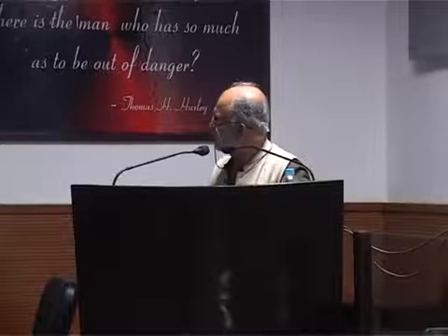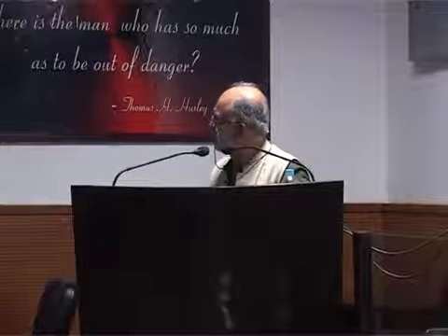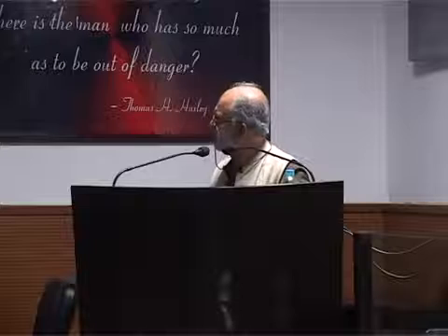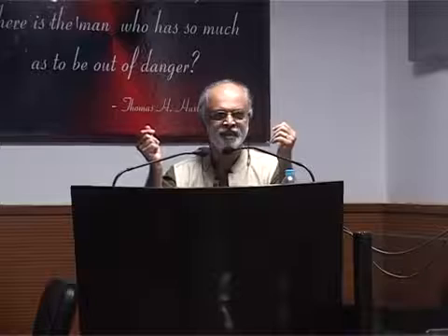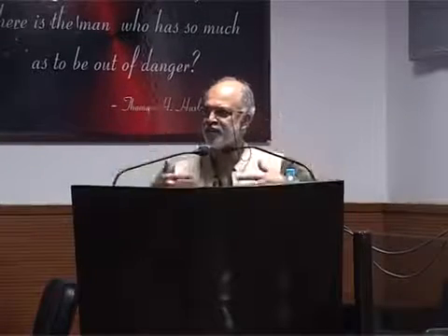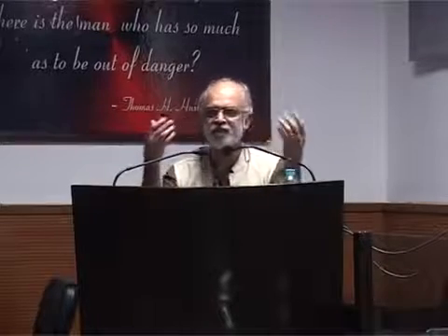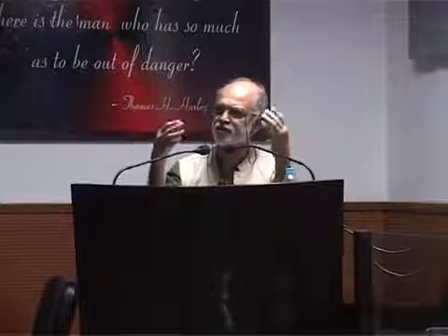A symmetrical collapse of the cavity is what was explained to you of the damage due to cavitation phenomena. When you have a solid surface, when the cavity size goes on reducing, the liquid will start rushing from all the directions to fill up that vacant space as a result of reduction in the volume of the cavity. Liquid is approximately 1000 times more dense than vapor. As a result, a huge amount of momentum is associated with this onrushing liquid. Now this momentum will keep on compressing the cavity, and the cavity compresses at a velocity which is higher than the velocity of sound, which is 1500 meters per second.